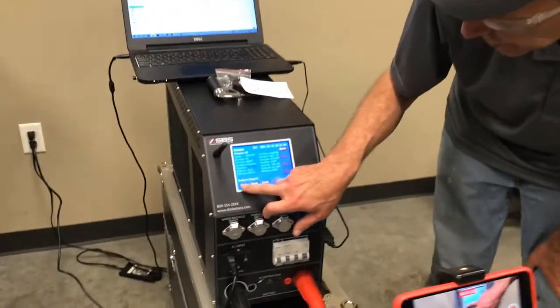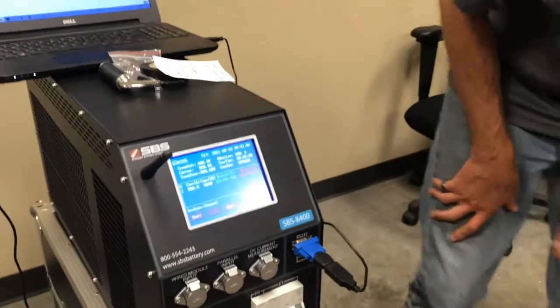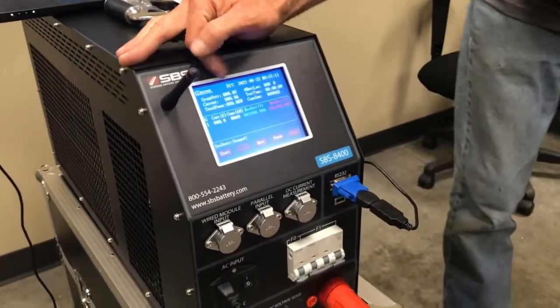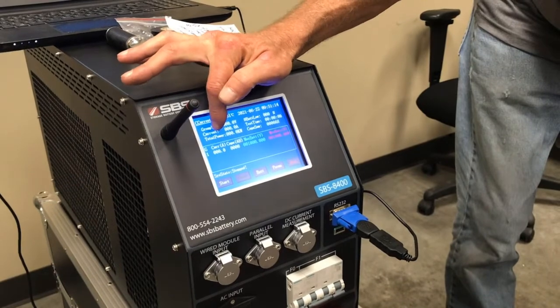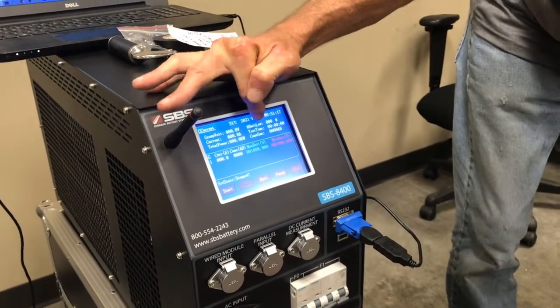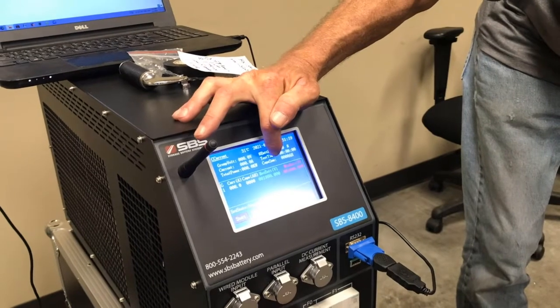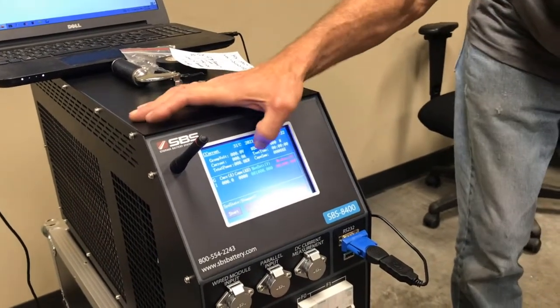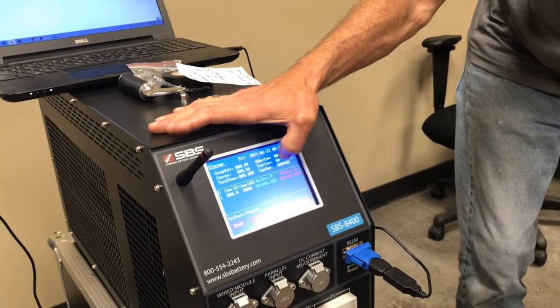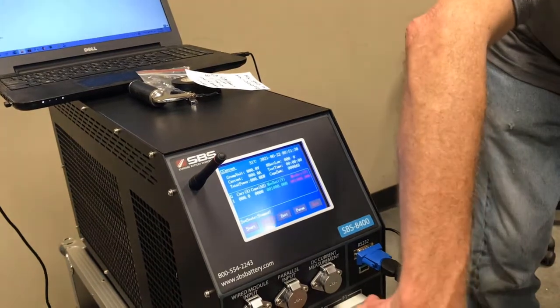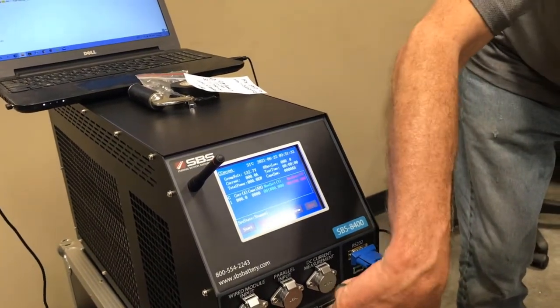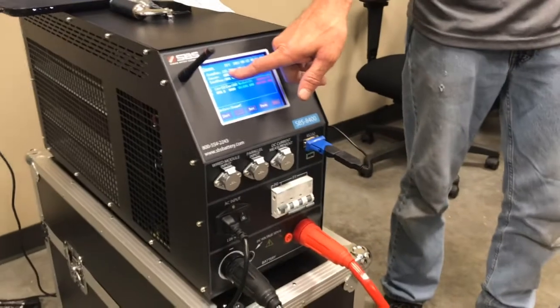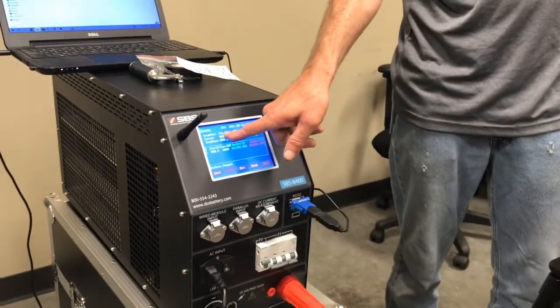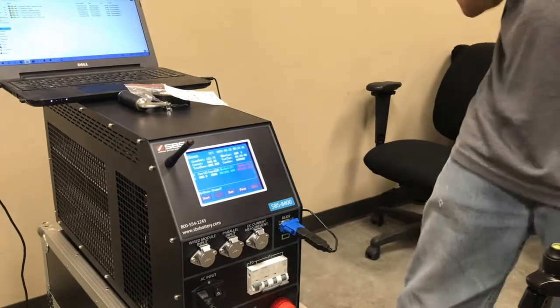Now that my DC battery is connected into my load bank equipment, I come over to the unit, I press the start button, I get a summary screen at the top of the screen. Group voltage, current, total power being consumed, number of battery lows, test time as the time progresses, and amp hours removed. So it'll cumulatively add up the amp hours removed from the battery. As soon as I turn on the F0 switch, I see my group voltage of my battery system show up on the load bank. What that does is that connects the battery to the load bank so the load bank can start measuring the values.